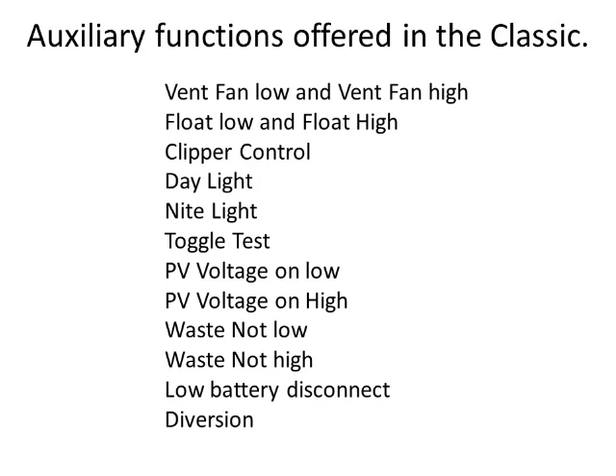For instance, diversion with the manual relay, if it's a big load, the minute it kicks in, it could drag the battery voltage down. So we've put a delay and a hold. So we wait for however many seconds or minutes that you program, and then we also hold the relay on as a delay for however long you've programmed it as well.